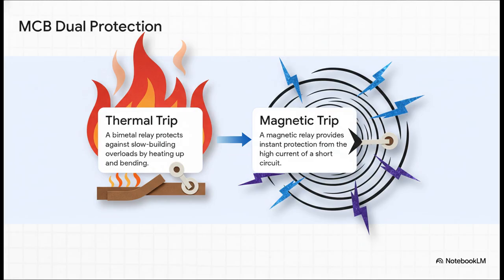This is where the MCB is just so clever. It basically has a two-part brain to fight both of our villains. For those slow-building overloads, it has a thermal trip — inside there's a little strip made of two different metals stuck together. As the circuit overheats, the strip gets warm, and since the two metals expand at different rates, it bends until it bends far enough to physically trip the switch. But for the sudden, explosive violence of a short circuit, that needs a much faster response: a massive rush of current creates an instant, powerful magnetic field that yanks the switch open in a fraction of a second. It's two totally different solutions packed into one elegant little device.